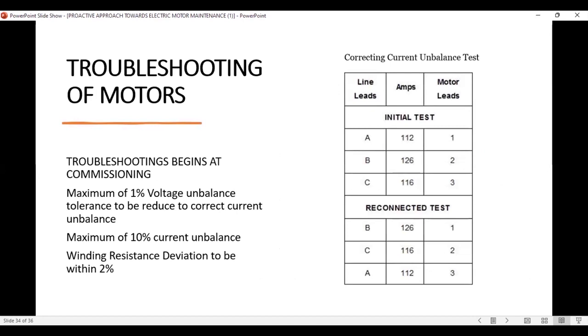So how do you correct imbalance? When you have imbalance, you must establish whether it's from the grid system or from the motor. If it's from the motor, you have to replace the motor. If it's from the grid, you have to correct it from the grid. For this one, you have phase one drawing 112, phase two 126, phase three 116. You move the leads of the cable and swap them to different phases. If you observe that one phase is consistently high even after swapping the leads, then you know that it's coming from the grid, or from your whole power reticulation system. Maybe there is voltage imbalance which is causing the current imbalance. Next slide, please.